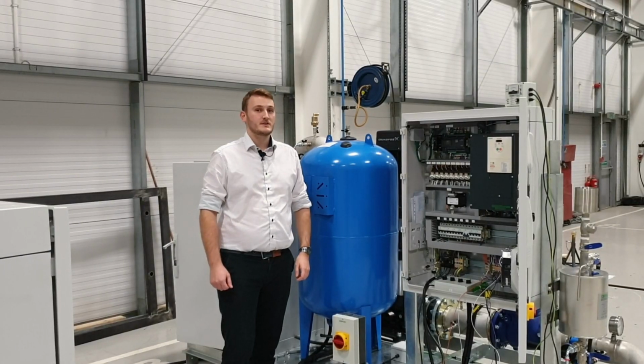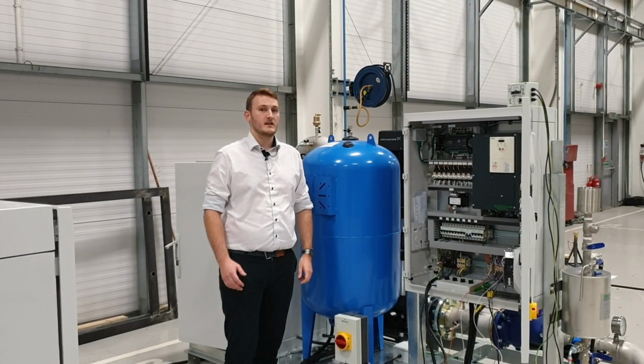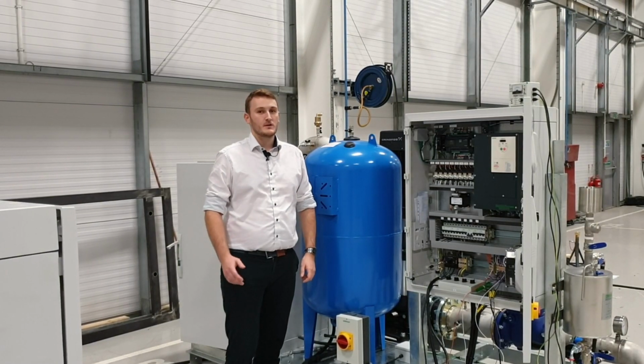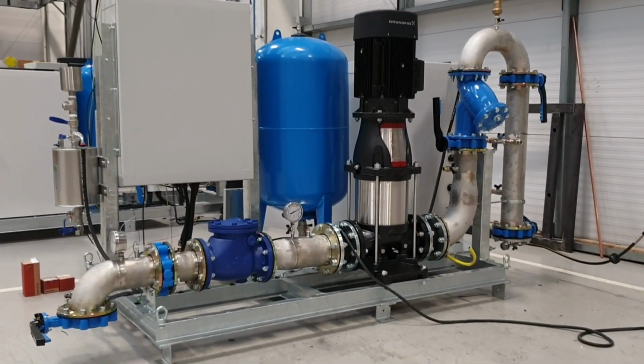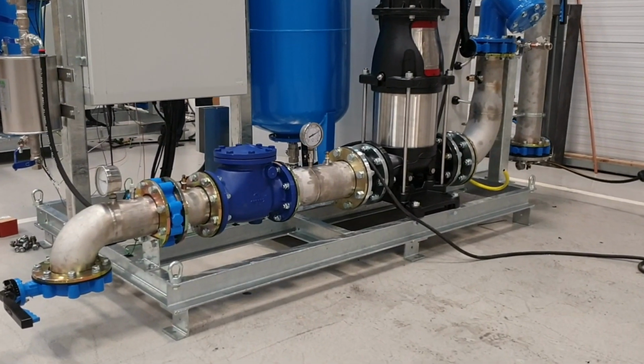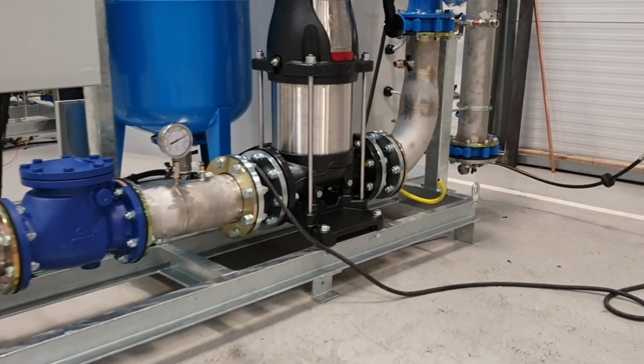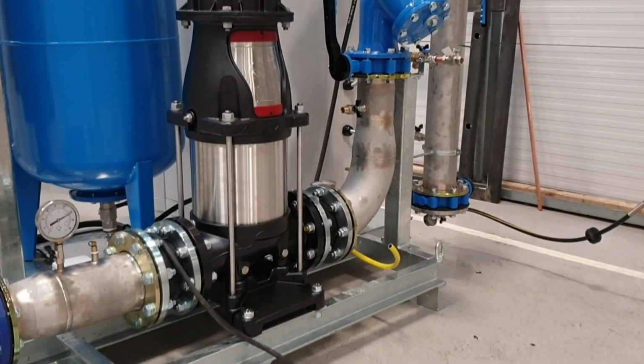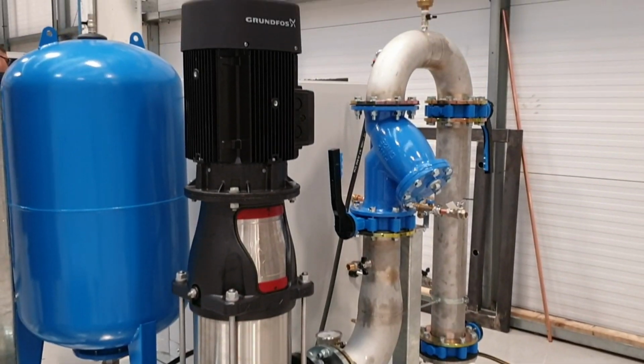Under normal operation, both pumps will be operating at half capacity. This means that we can operate them under the best efficiency. However, with the redundancy capabilities, it means that if one pump were to fail for any reason, then there is no loss throughout the system.